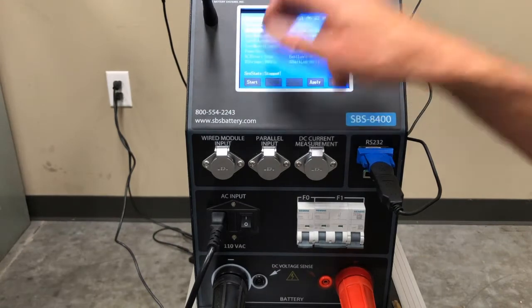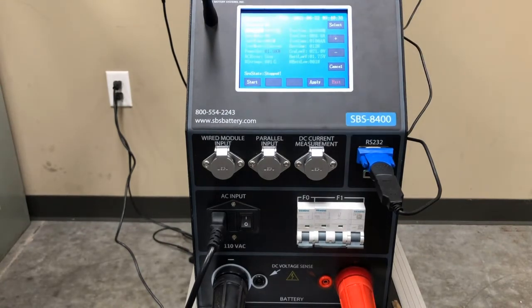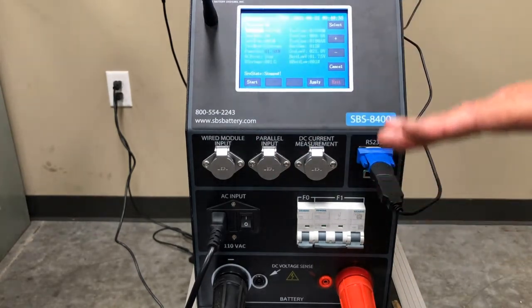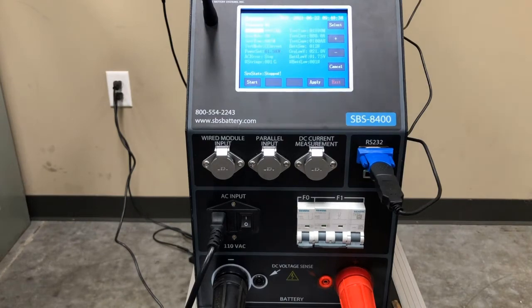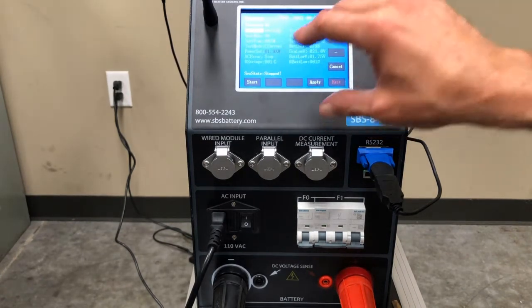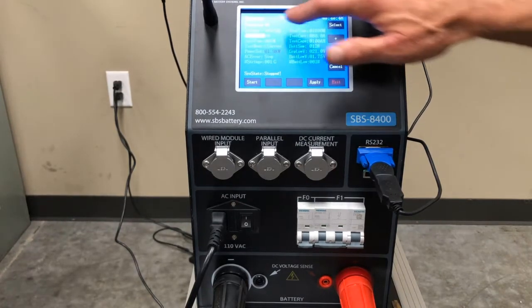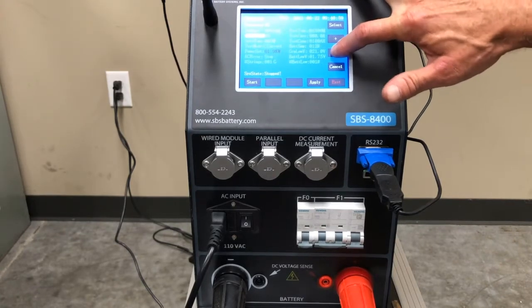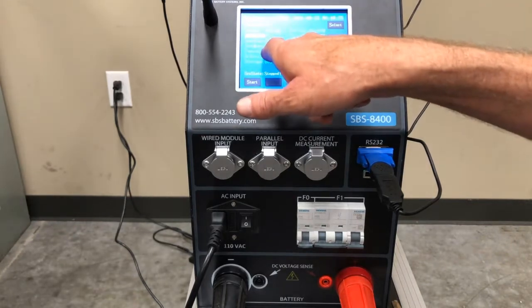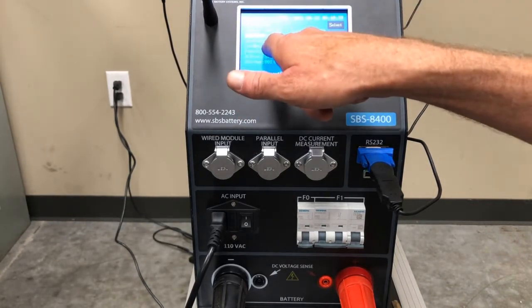Okay. And my hour rate would be the 3 hour rate, because that's the value that came from the battery data sheet. Right. Okay. That's not how long my test is going to run. That's not when it's going to shut down. That's what the battery's 100% rating at that rate of discharge from the performance data is. Okay. So I'm set at 97 amp hours. I'm going to come down this and change it to the 1 hour discharge rate, because that's what I pulled from the data sheet, 97 amps for 1 hour. I'm going to save data.